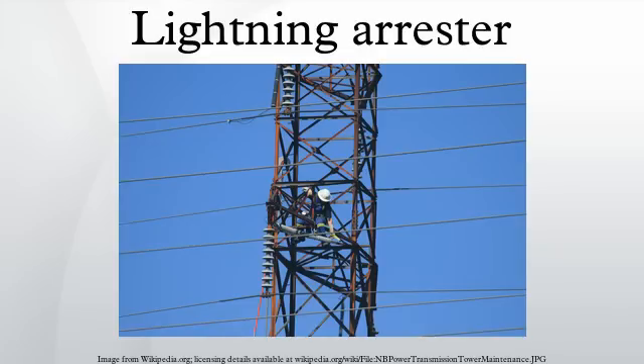Smaller versions of lightning arrestors, also called surge protectors, are devices that are connected between each electrical conductor in power and communication systems and the Earth. These prevent the flow of the normal power or signal currents to ground, but provide a path over which high-voltage lightning current flows, bypassing the connected equipment.